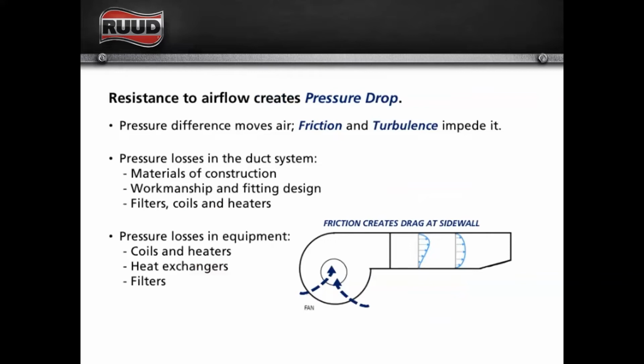So in that airflow, whether it's in the return or the supply, any resistance creates a pressure drop. And that pressure drop is typically caused by friction or turbulence. And that friction could be the air moving through our cooling coil. The friction is the air moving through registers and grills. The friction is also just the drag on the sidewall of the duct. So as the air is moving through the ductwork, everything in that system is slowing that air down and making it harder for the air to move through the ductwork to get either to or from the conditioned space.